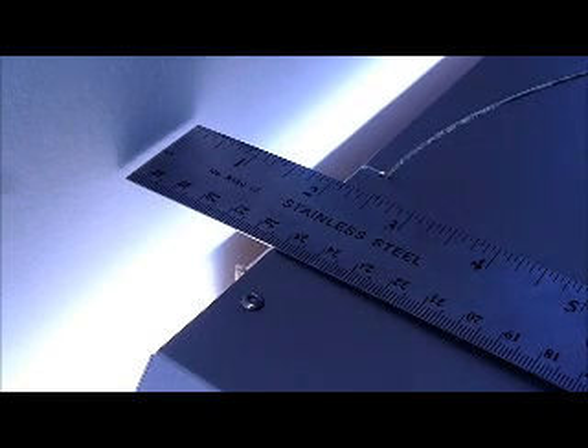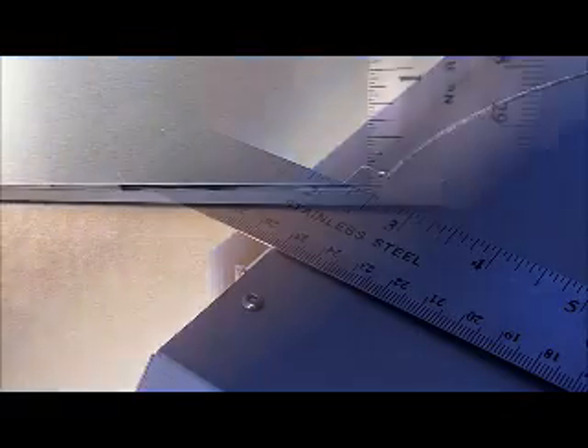The next thing you want to do is make sure you've got appropriate clearance on the side of the fixture. Hot air exits the side of the fixture opposite the cord itself, and so you want to have at least 2 inches between the side of the fixture and the wall and/or canopy that may be to the side of the fixture itself. Again, minimum of 2 inches, and ideally more.